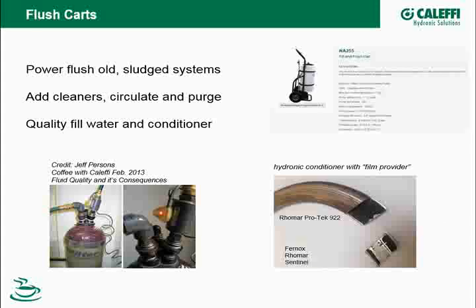So it doesn't hamper the heat exchange efficiency, but it does protect that metal from being attacked. So if you do have water that has a pH that's out of whack, it won't start going after that metal because it's got a little layer of protection on it. So that's what you want to find. And there's a lot of good brands out there. Fernox is a brand that has both the cleaners as well as the different inhibitors, Rhomar and Sentinel. And they also all have test kits available that match the fluid, so you can go back and test. Sometimes you have to boost the inhibitor. If the inhibitor is being used up and you have to boost it, it's saying there's something going on in the system. Most of the time you've got oxygen getting in there that's using up or compromising those inhibitors.